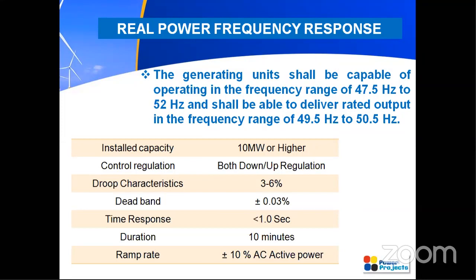And not only that, it may have some governors or frequency controllers, and the droop characteristics of those frequency controllers or governors should be from 3 to 6% only, and the deadband should not exceed plus or minus 0.03%. This is a very important condition about the frequency control. And a very important thing is that whenever there is a frequency variation, and if the frequency deviation exceeds 0.3 hertz, then within 1 second your generating unit should have the capability to provide an immediate response of real power primary frequency response. It should be given within 1 second.